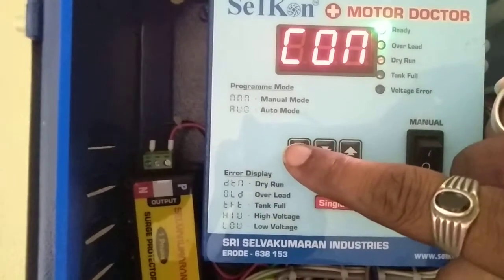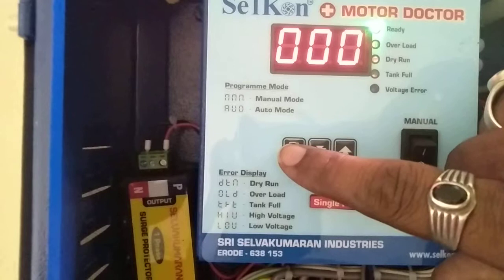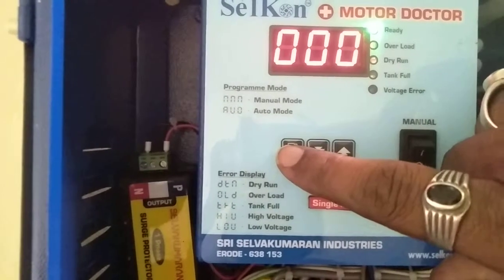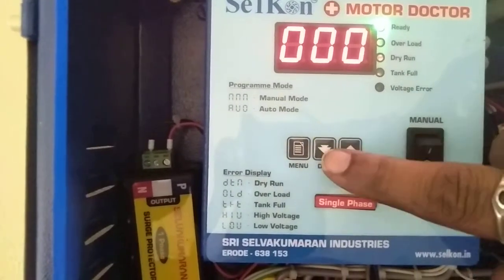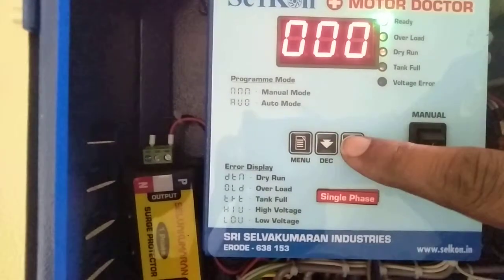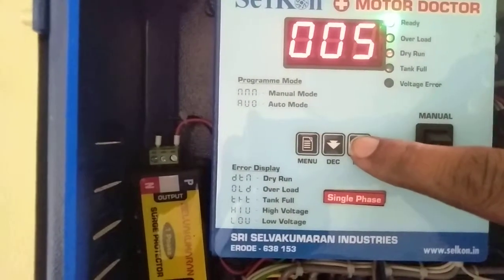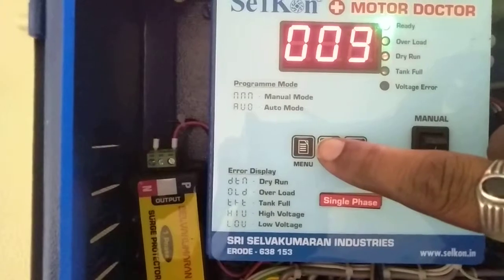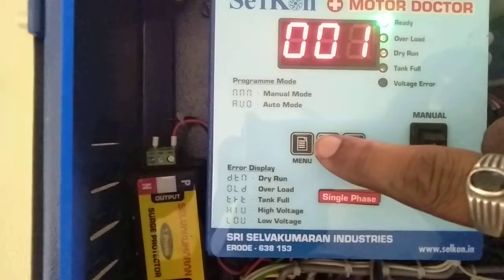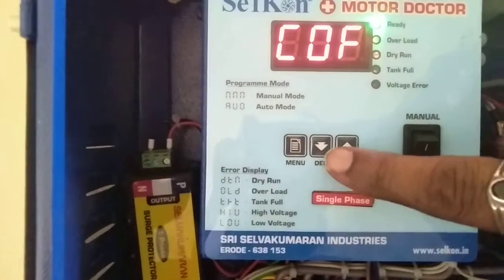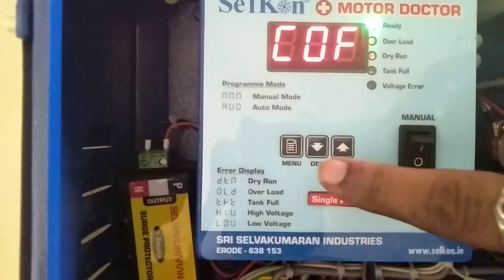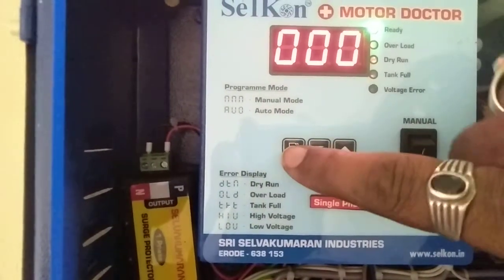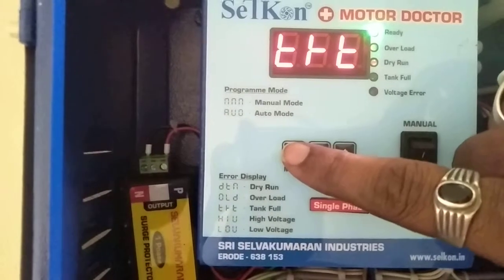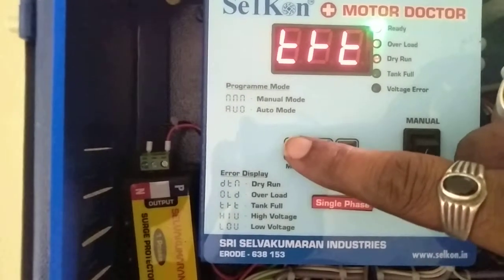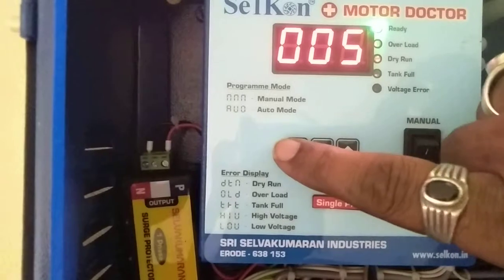Then CON. Suppose the borewell has only limited water, so it has to run for 10 minutes, 20 minutes or 30 minutes. Then we have to fix the on time and off time. So if you have to run the motor for half an hour, you have to fix 30 as the on time. So automatically the motor is on for 30 minutes. Then the off time. Suppose you have to give it 2 hours rest, you have to fix 120 for the off time. Then in dry run time, if any problem arises, within 5 seconds the motor switches off automatically.